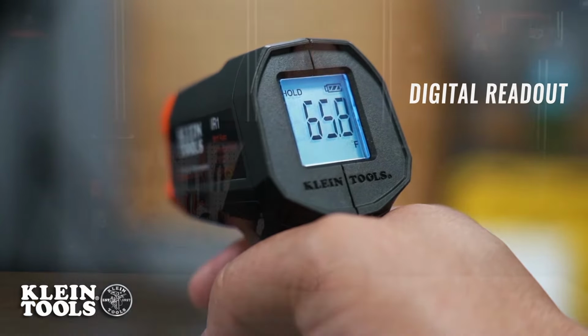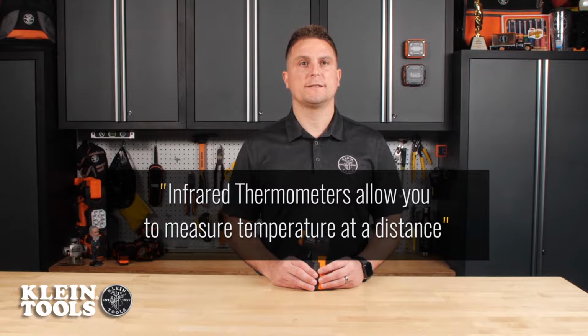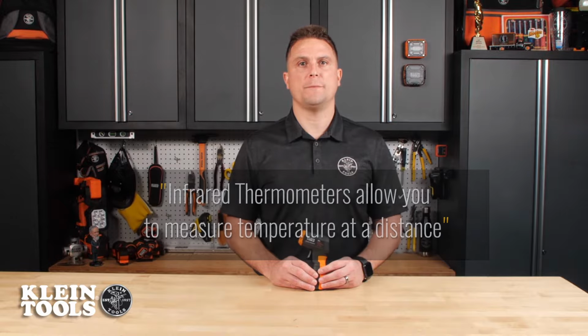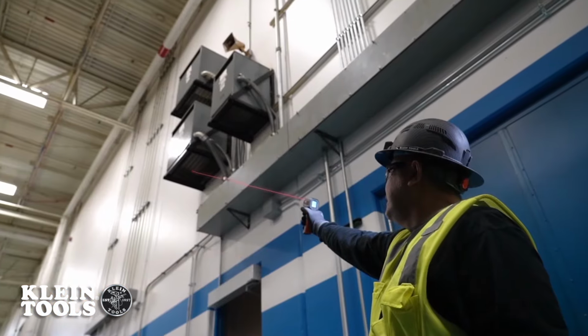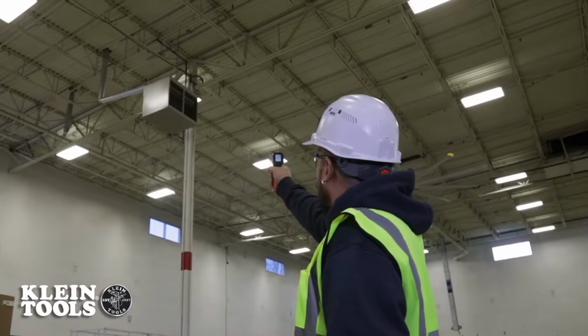One major advantage of infrared thermometers is that you can measure temperature at a distance. This is especially useful when the target object is out of reach, for example overhead electrical or HVAC equipment in a warehouse, or in situations where direct access could be hazardous, such as on live operating industrial equipment.